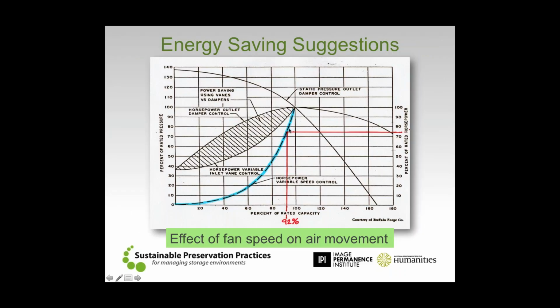And as we do that, notice as we drop down this curve, by reducing that airflow by 10%, we've also managed to save almost a quarter of our total energy. Now that's a pretty good relationship, right? Most of us would say, well, 90% of airflow going through a space on a number of days, anytime we're not at a peak day or the hottest and wettest day of the year in terms of summer conditions, 92% of total airflow is going to be more than enough to still achieve what's going on in the space. This comes back to experimentation, but oftentimes it holds true. Well, if I can run at 90% of total capacity but save 25% of my energy, that's not bad.